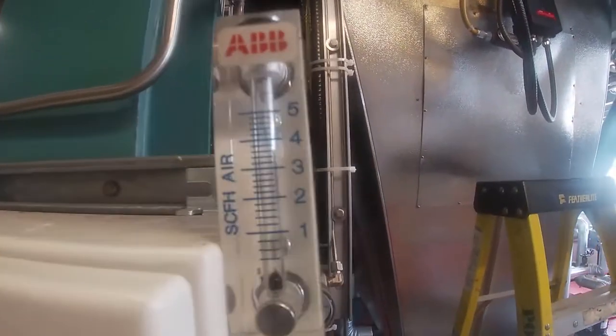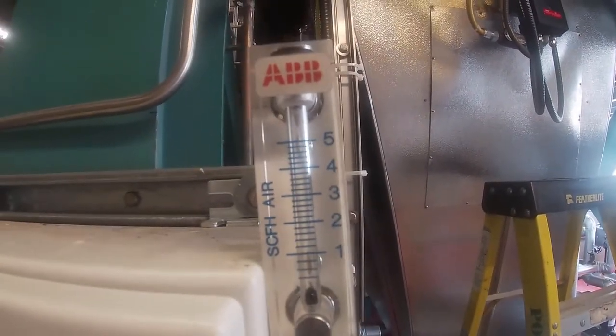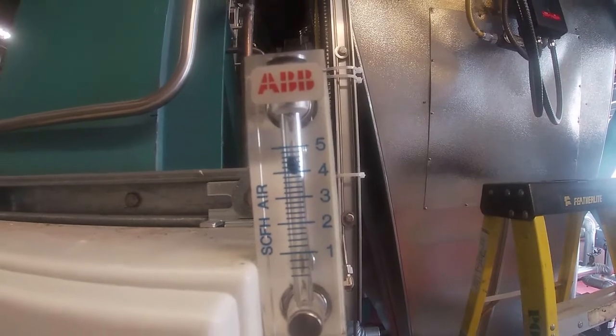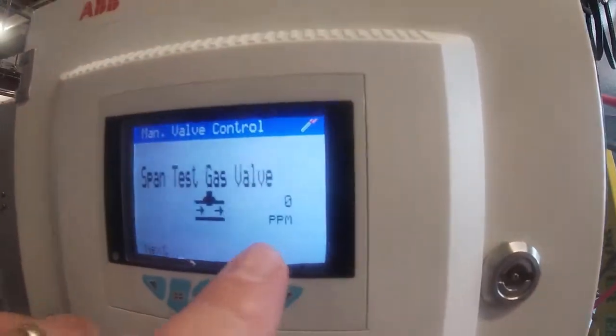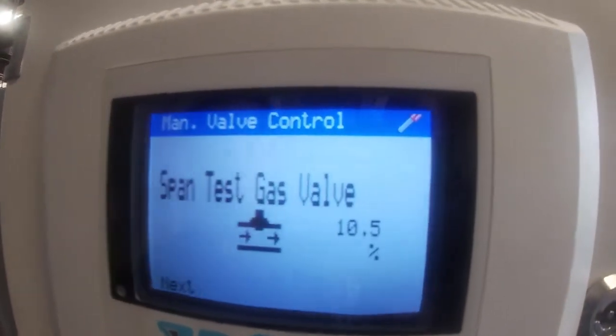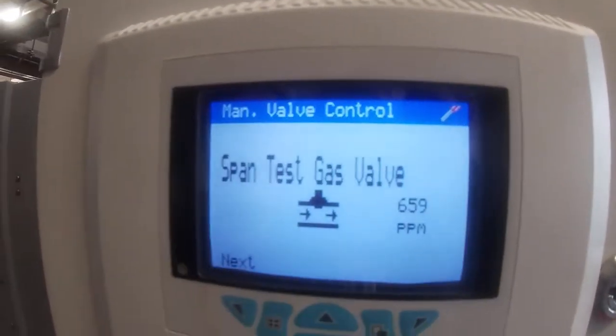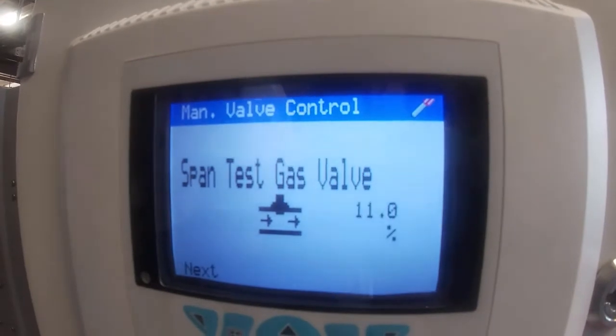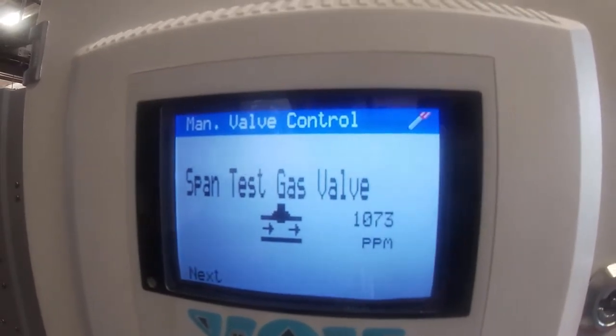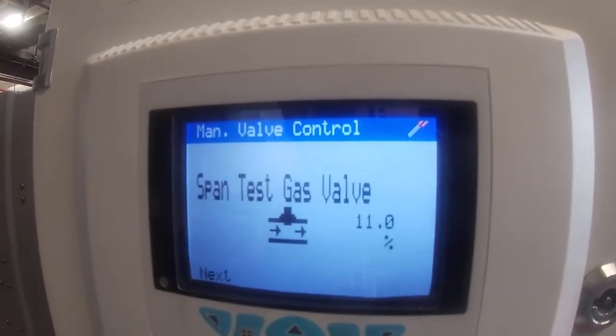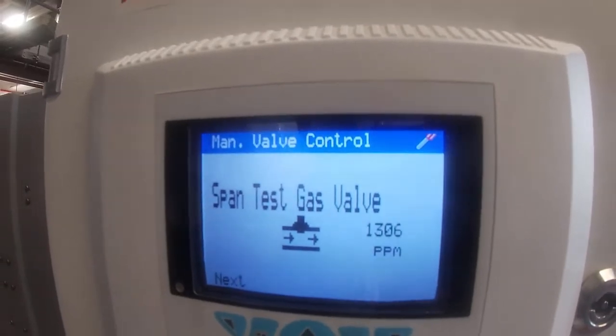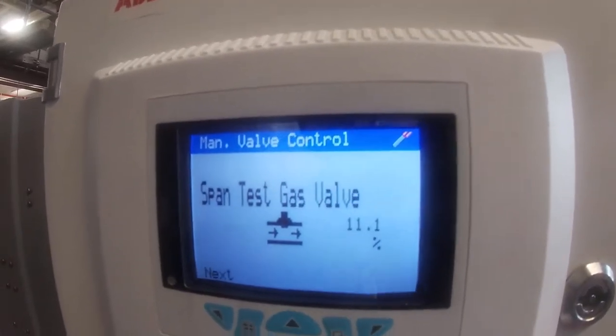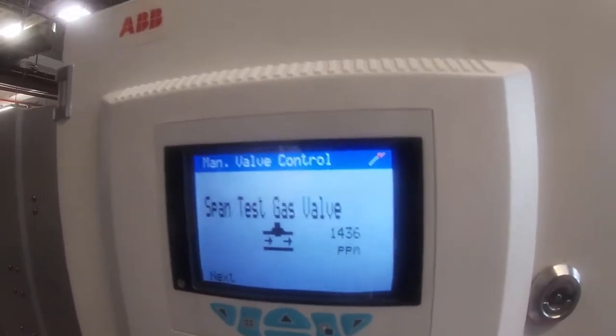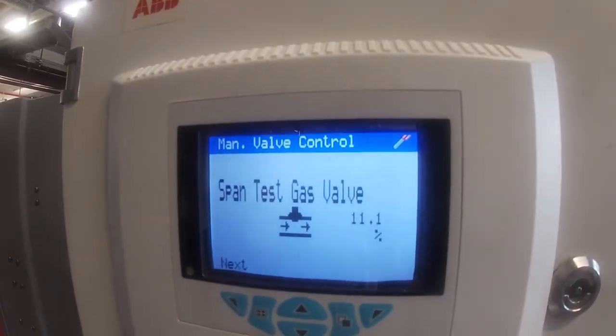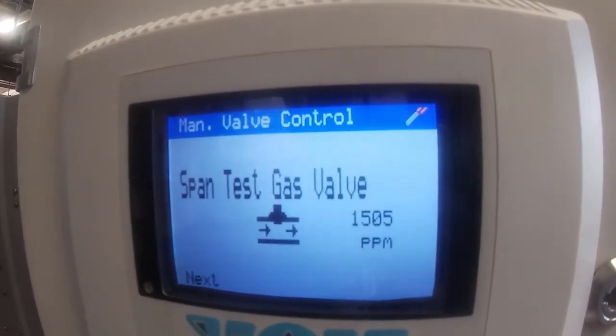And I'm going to hit the up arrow to open that gas valve, and bang, up she comes, and I've got 4.5 cubic feet, and you can see now that the span gas is on its way down. Now, I forgot to write those values down. The zero was 1.3, and this was at 0, right?